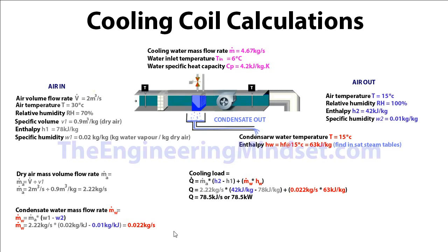From all this we can then calculate the cooling load, represented by Q. That formula is the mass flow rate of the air multiplied by the difference in enthalpy across the two airstreams, plus the mass flow rate of the water multiplied by the enthalpy of the condensate water. The numbers are color-coded so you can trace them through. Dropping these numbers in, this comes out at 78.5 kilojoules per second, which is also 78.5 kilowatts — meaning this cooling coil is extracting 78.5 kilowatts of thermal energy from the airstream.